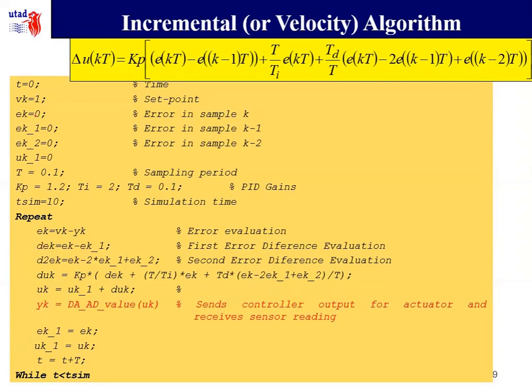The algorithm for the velocity is more or less the same as before. What changes is that now we got the difference of the error and the second error difference. And of course, instead of evaluating the absolute value, we evaluate the delta, delta U. And then we just become this delta U and update the previous value of the controller. This implementation has an advantage because as we don't have the sum of the integral, this implementation is less sensitive to integral windup.